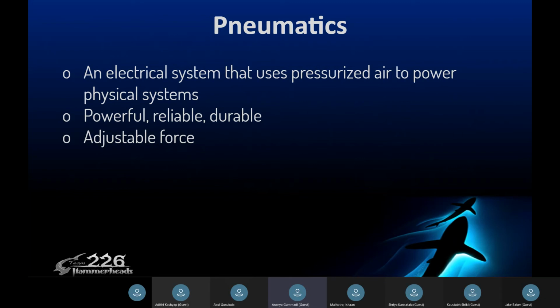A pneumatic system is comprised of a couple of key components, which we'll go over in the next slides, but I'll just briefly go over them right now. An air compressor is used to produce the compressed air. Storage tanks hold the air. A pressure sensor senses the air pressure and allows the software to turn off the compressor when it passes a certain threshold. Relief valves connect to the compressor and release air if the pressure gets too high.